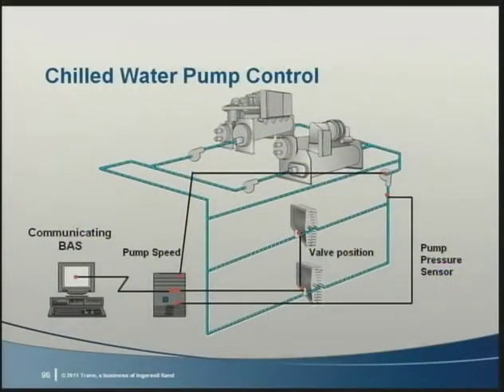A common strategy is to operate the pump to supply a constant system pressure differential at the most remote air handler. If all valves in the system are partially closed, the pump speed and pressure set point are too high. Here's a better way. It's a cascaded control loop. That is, we have a pump speed determined by providing a specific pressure leaving the pump. This control is active all the time.